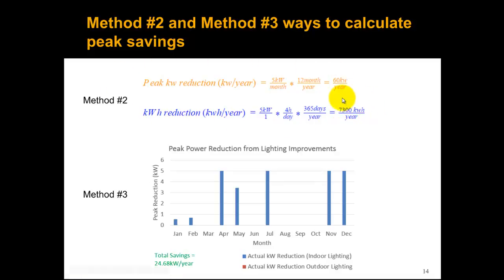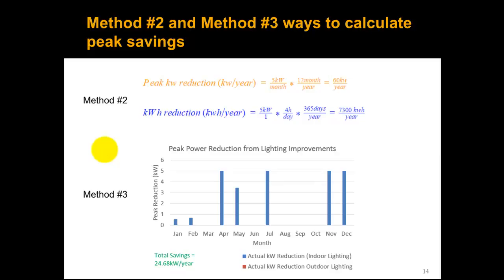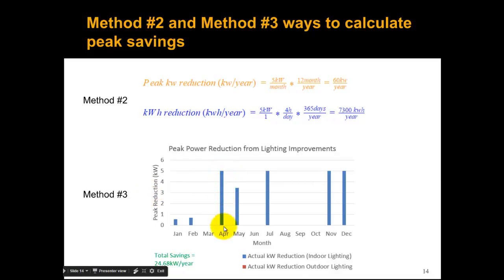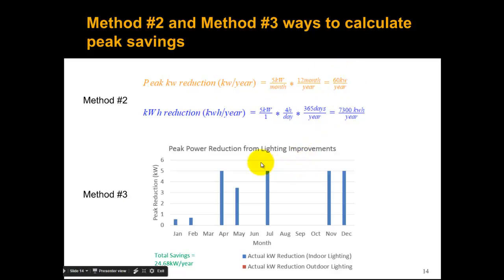When we actually go through in Excel and reduce the kilowatts during those times and look at the peak power reduction, in some months we do get that full five kilowatts — for example in April, July, November, and December. But in some months we don't get any kilowatt reduction at all. You have to be very careful when you assume a full kilowatt reduction with ECMs like this. Method two assumes 60 kilowatts per year, but the actual peak kilowatt savings using method three is 24.68. And we're not getting any kilowatt reduction from outdoor lighting, so that assumption was correct.